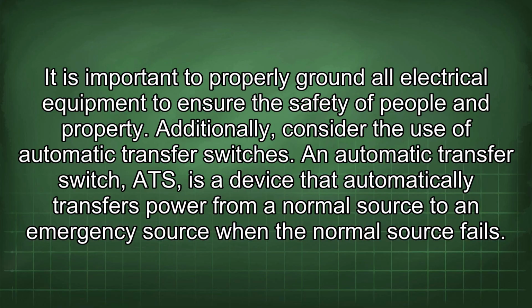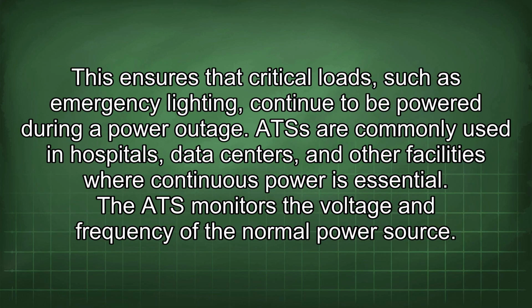Additionally, consider the use of automatic transfer switches. An automatic transfer switch, ATS, is a device that automatically transfers power from a normal source to an emergency source when the normal source fails. This ensures that critical loads, such as emergency lighting, continue to be powered during a power outage. ATS are commonly used in hospitals, data centers, and other facilities where continuous power is essential.